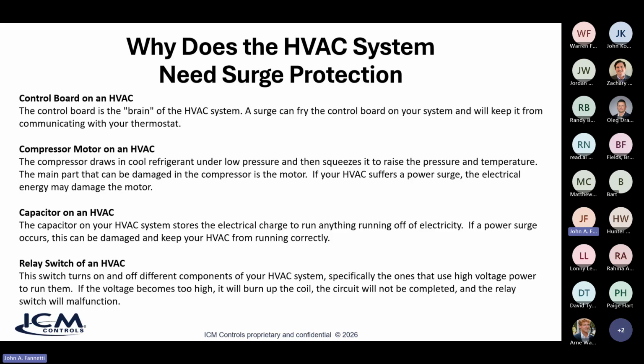You never want to have that situation where your equipment just randomly goes down because of a surge. And there's also relay switching of the HVAC switch that turns on and off the components in your HVAC systems, like the contactor, that can get fried. So there's a lot of things in the HVAC system that can be damaged by a surge, mainly being the control board and the compressor. Those are the two things you really need to protect.